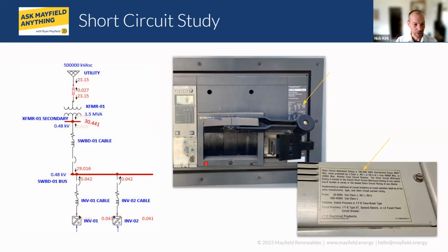And so we take all of this and we integrate it into our ETAP model, and then we can run the short circuit study, which will either verify or cause the need to change certain equipment through the system. And like I mentioned before, we like to do this at a certain point in the design so that we can capture issues before equipment procurement. And so in this particular case, on the right hand side, we're just pointing out the short circuit amps interrupting capacity of the specific devices, and then also the equipment ratings. So this is taking existing equipment into account as well. So you're going to put in some existing equipment, and then we're adding PV to this in some cases. And so it's not always the case that we get to change switchboard 1 or something, for example. It's like that's what it is, and we have to do the study to figure all that out, right? Yeah, exactly.